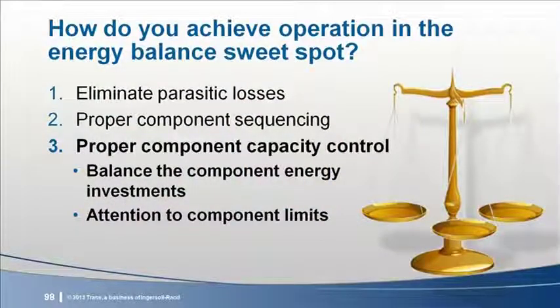For that reason, and to prevent undue wear on system mechanical components, we want our system control to place a priority on stable operation. Let's look at the last key to achieving balanced and optimum system efficiency. That is component capacity control. As we suggested previously, the key to system efficiency is balancing the energy investment in each component at that moment's operating condition, all while avoiding operation outside of any of the component's acceptable operating range.